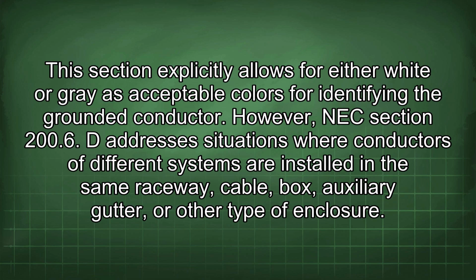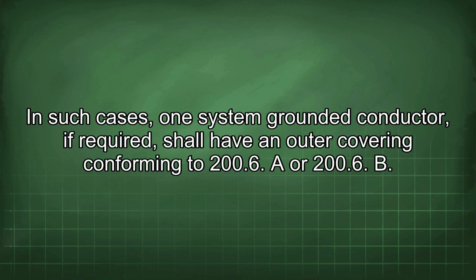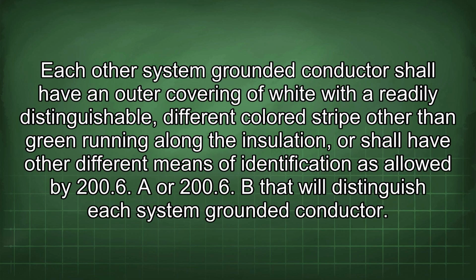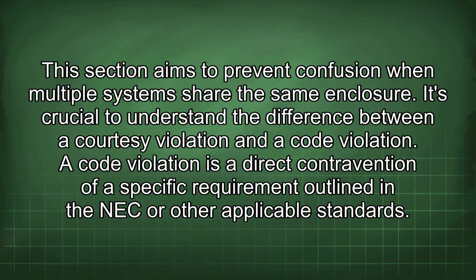However, NEC Section 200.6(D) addresses situations where conductors of different systems are installed in the same raceway, cable, box, auxiliary gutter, or other type of enclosure. In such cases, one system grounded conductor, if required, shall have an outer covering conforming to 200.6(A) or 200.6(B). Each other system grounded conductor shall have an outer covering of white with a readily distinguishable different colored stripe other than green running along the insulation, or shall have other different means of identification as allowed by 200.6(A) or 200.6(B) that will distinguish each system grounded conductor. This section aims to prevent confusion when multiple systems share the same enclosure.